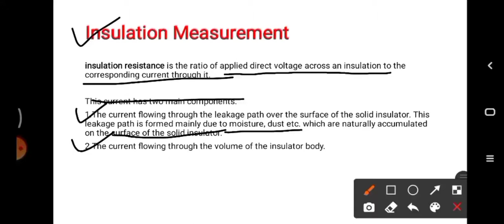When DC voltage is applied to insulation, current starts flowing through the insulation. This current has two main components. The first component is current flowing through a leakage path over the surface of the solid insulator. This leakage path is formed due to moisture and dust, which normally accumulate on the surface of solid insulating material. The second component is current flowing through the volume of the insulator body.